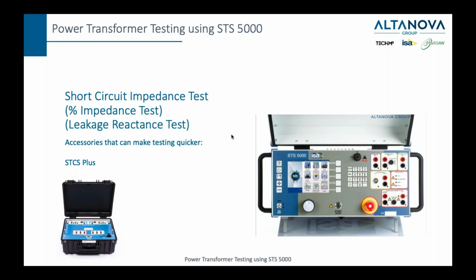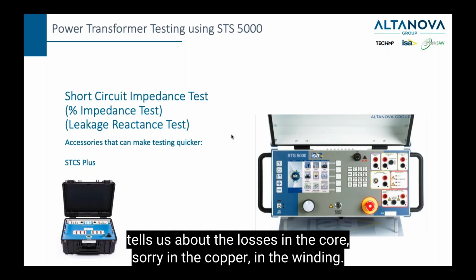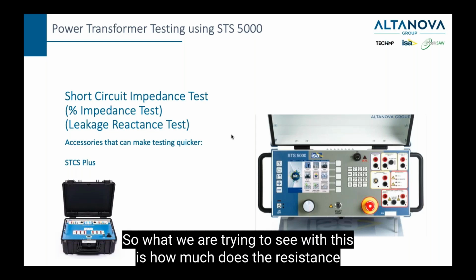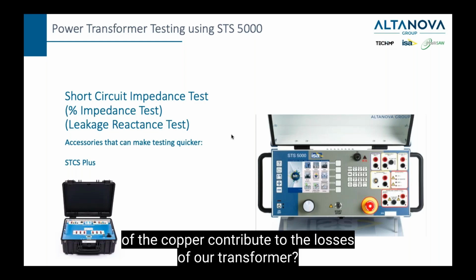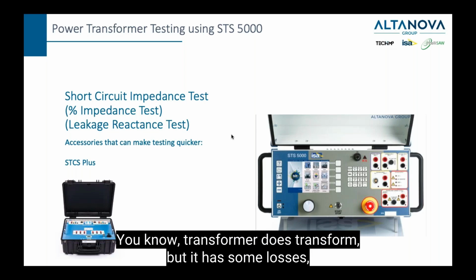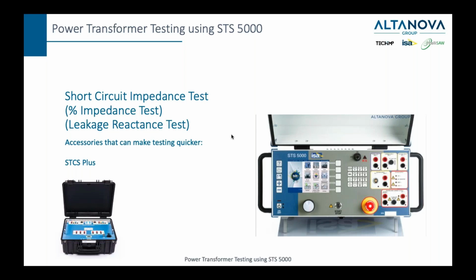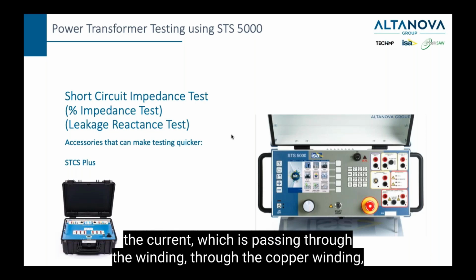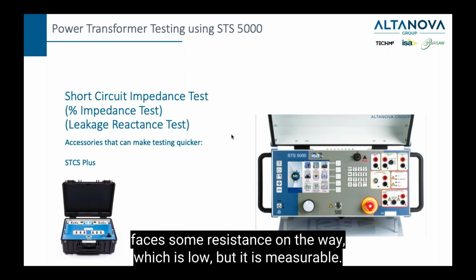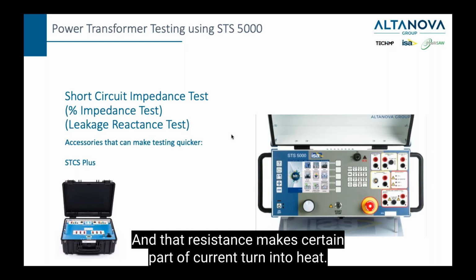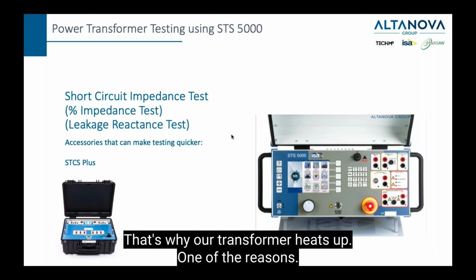Short circuit impedance test tells us about the losses in the copper, in the winding. So what we are trying to see with this is how much the resistance of the copper contributes to the losses of our transformer. You know, a transformer does transform, but it has some losses. It is not a perfect device, because the current passing through the copper winding faces some resistance on the way, which is low, but it is measurable, and that resistance makes a certain part of the current turn into heat. That's why our transformer heats up, one of the reasons.